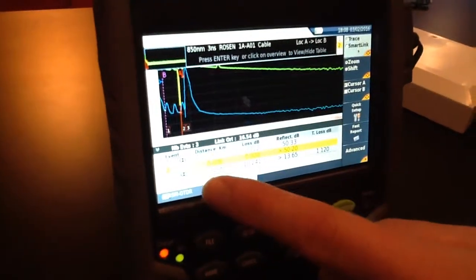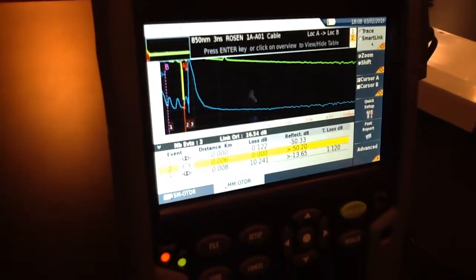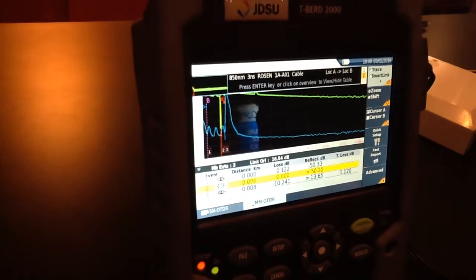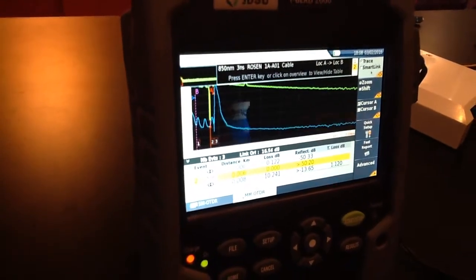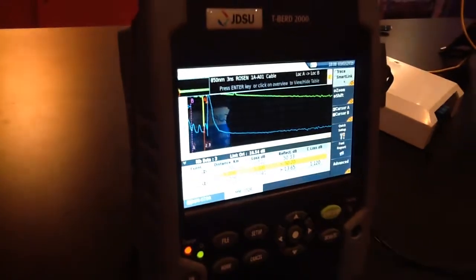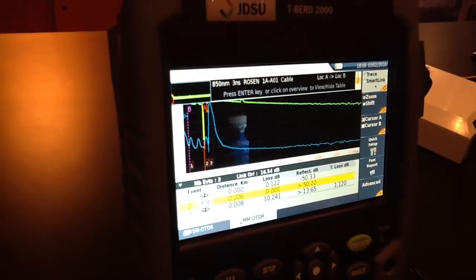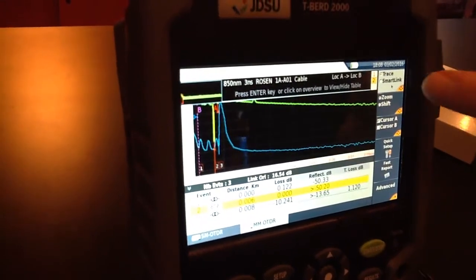Here's a screenshot of a typical trace that you would see with an OTDR. We've done a couple things. Number one, we've included a summary of all the events down below with an icon showing what's actually going on at each one of those events. You can see I've highlighted Event 2 here — it's telling you that it's .006 kilometers away, and that's actually a connector. There's a certain amount of loss and a certain amount of reflectance happening.